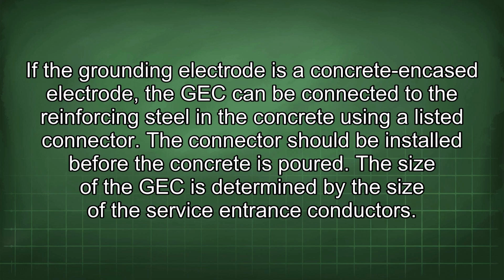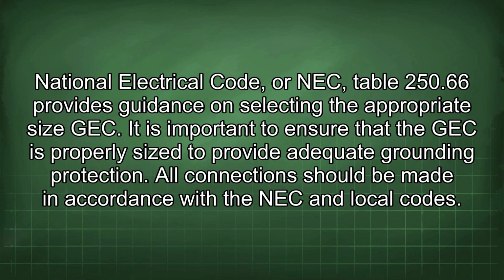The size of the GEC is determined by the size of the service entrance conductors. National Electrical Code, or NEC, Table 250.66 provides guidance on selecting the appropriate size GEC. It is important to ensure that the GEC is properly sized to provide adequate grounding protection.